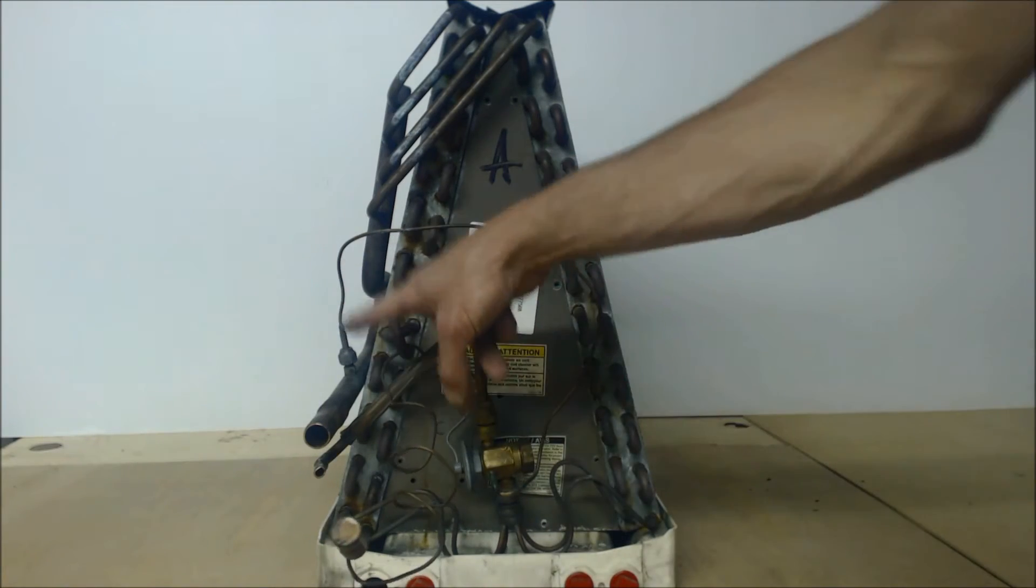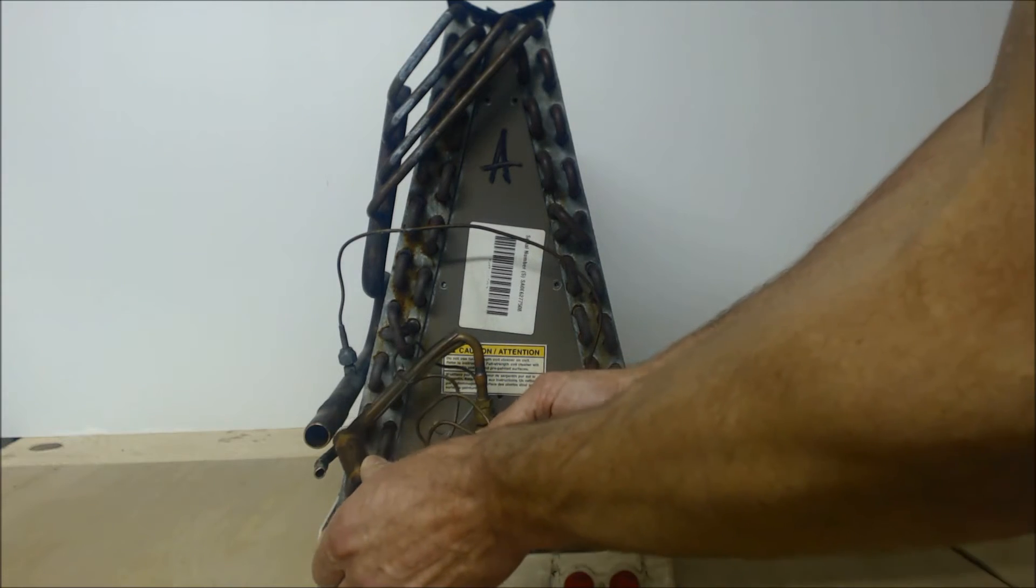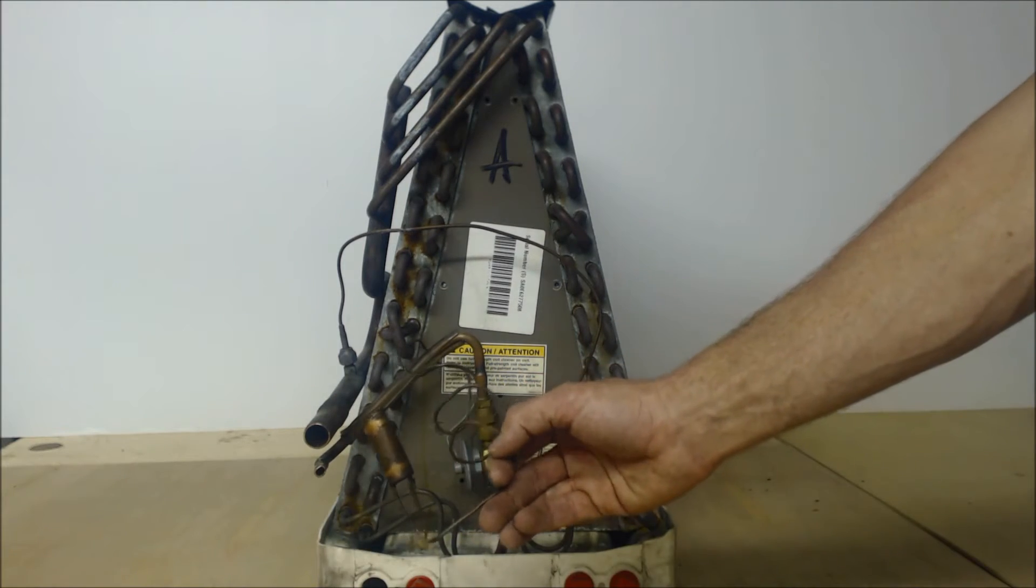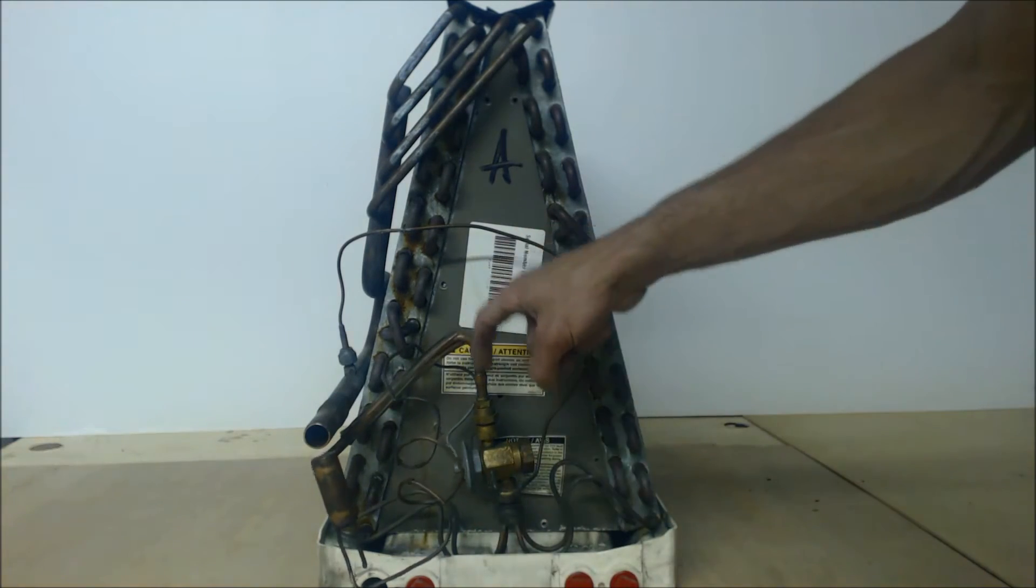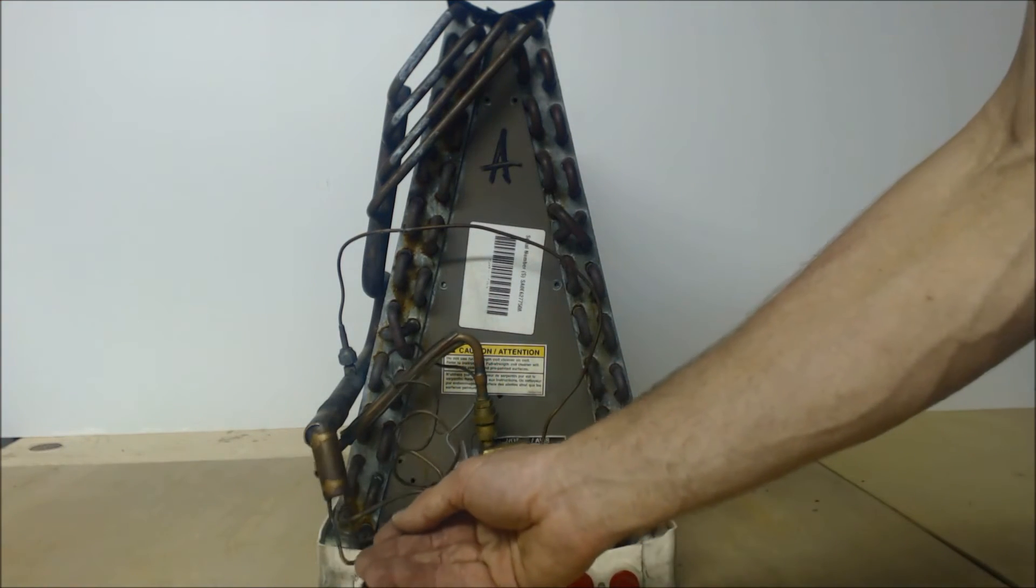The other thing that it takes into play is actually the pressure coming off of this TXV bulb. So it has the pressure coming in, the external equalization pressure, and the bulb pressure.